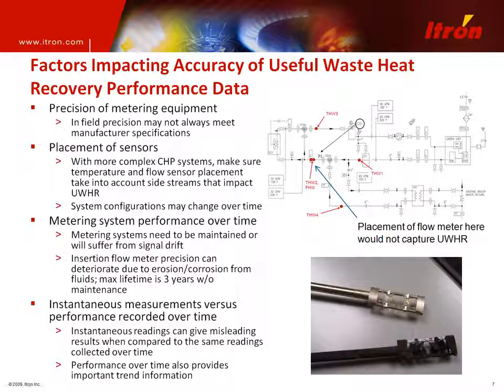Also take into effect that system configurations change over time, and so what you initially were metering may not be the same if there's a change in the process. Also, the performance of metering systems can change over time. You've got to really maintain systems, and so the bottom right-hand picture here is a new turbine meter on the upper part of that picture versus an older turbine meter. And again, there's nothing wrong with turbine meters. Turbine meters are a great application. You just have to be very careful to maintain them. And as Bowen mentioned earlier, water quality is critical. If you have systems with good water quality maintenance over time, your turbine meter is going to last much longer.